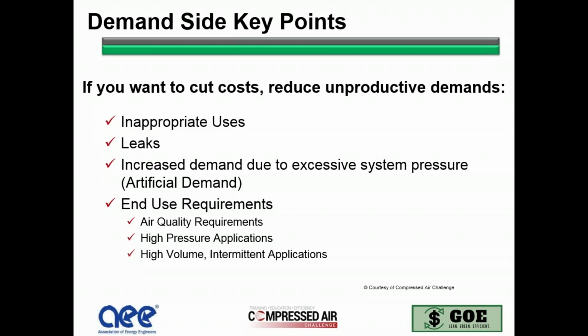For high pressure applications, sizing and providing the right pressure required is important. You need to be able to understand that. And then also the high volume intermittent demand applications. These are ones that put a lot of load on the system immediately for a short duration of time. And it's an excellent area for secondary storage to minimize that demand effect. And these are all also ones that we cover in both fundamentals and advanced.